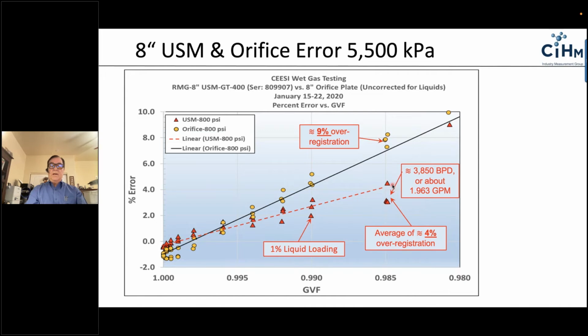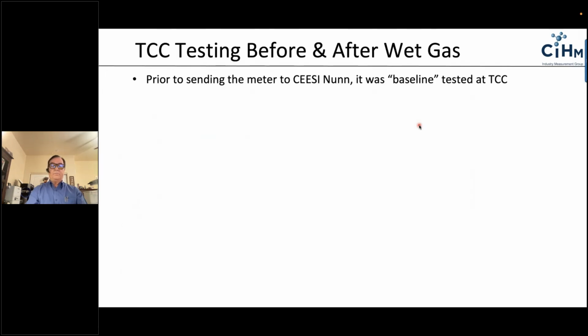As the liquid content increases even more, you'll see that the meter becomes a little more nonlinear, which is very common for ultrasonic meters. You'll also notice down here the orifice meter tends to under-register in the beginning. This is also not uncommon. Very traditional, very normal expected performance of both the orifice and the ultrasonic meter.